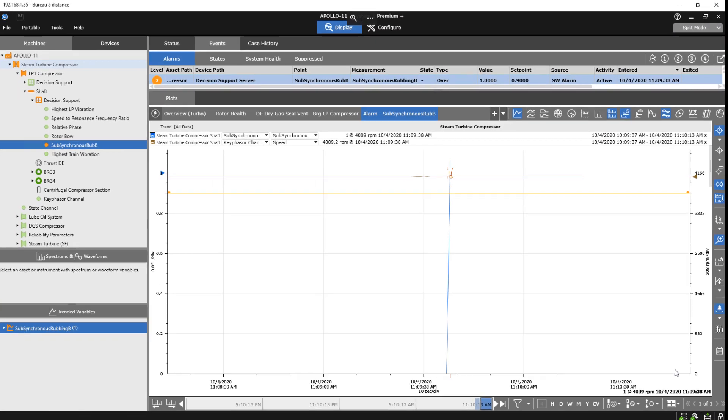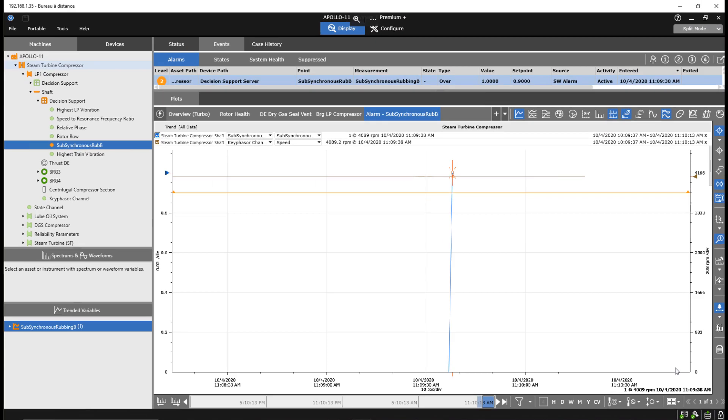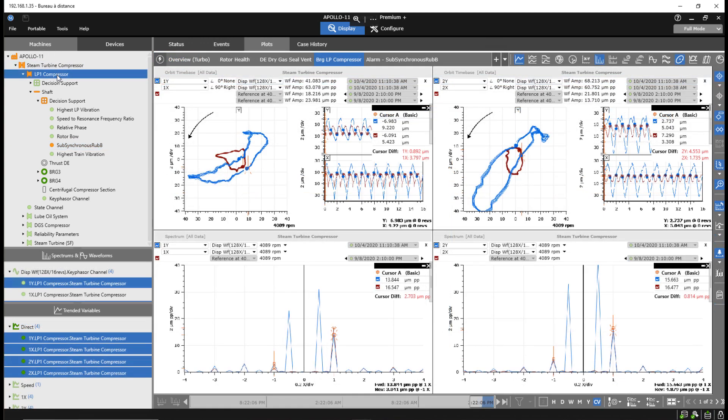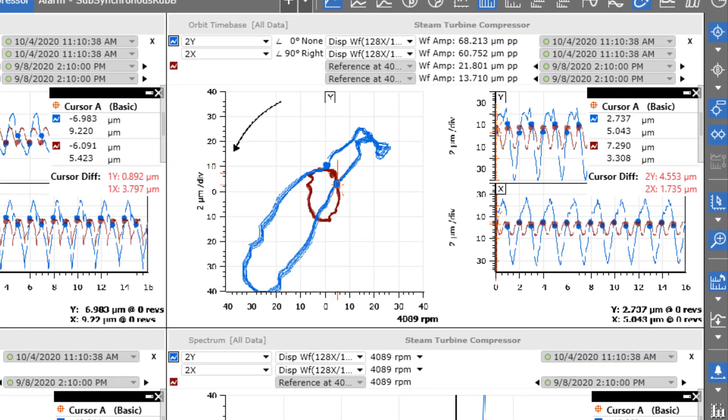The engineer then uses System One's visualization tools to confirm the diagnostic by decision support where high-resolution data sets are evaluated. The orbit plot shows the current orbit, which is colored in blue versus how the machine operated during a healthy non-alarm state, which is colored in brown.